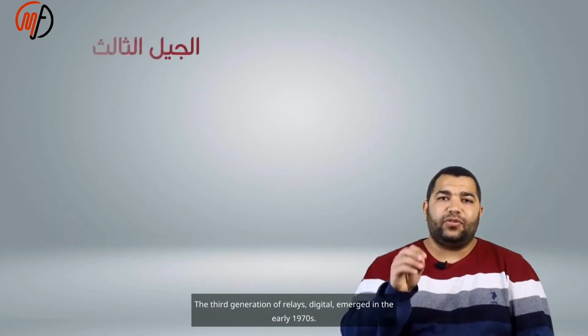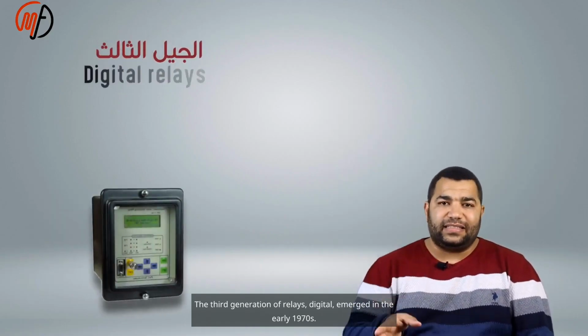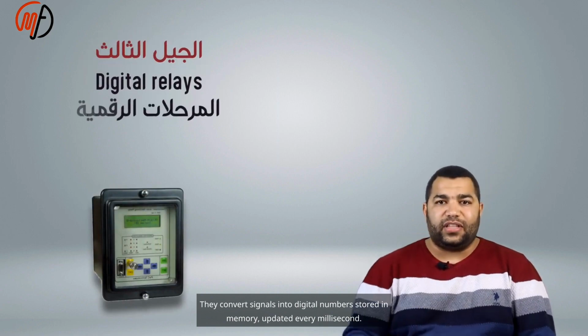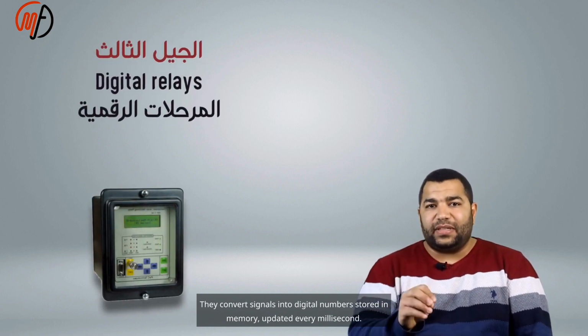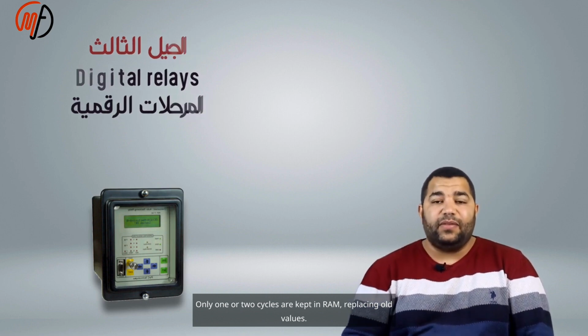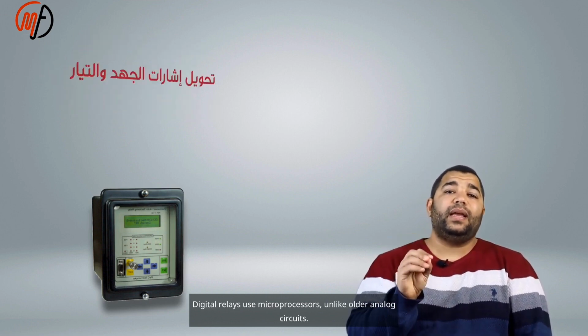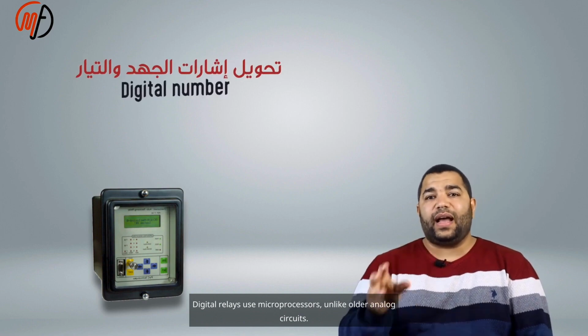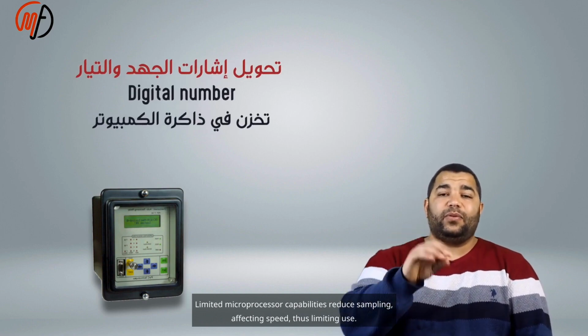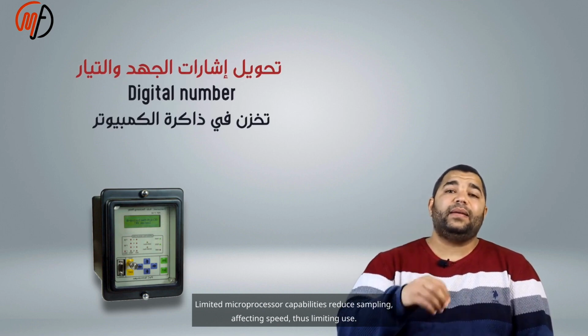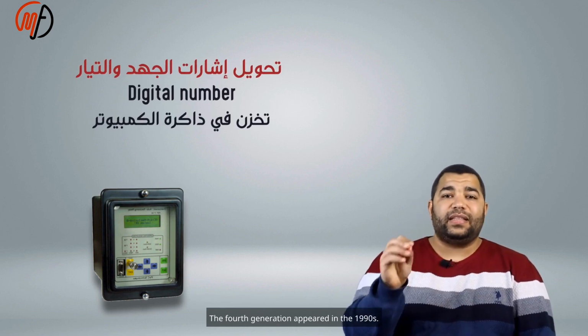The third generation of relays, digital, emerged in the early 1970s. They convert signals into digital numbers stored in memory, updated every millisecond. Only 1 or 2 cycles are kept in RAM, replacing old values. Digital relays use microprocessors, unlike older analog circuits. Limited microprocessor capabilities reduce sampling, affecting speed, thus limiting use. The fourth generation appeared in the 1990s.